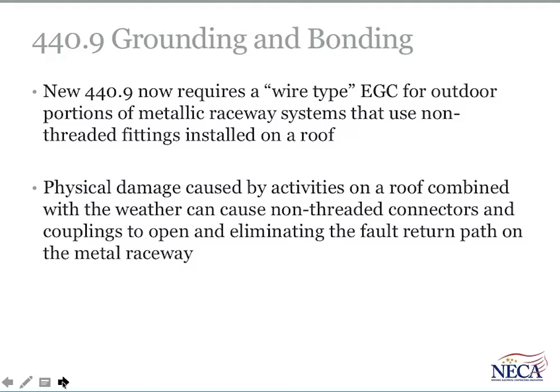So what that means is if it's intermediate metal conduit, rigid metal conduit, or EMT, and we're using compression-style slip fittings, the wire-type equipment grounding conductor is now required. The substantiation to drive the change was related to physical damage to a lot of those raceways being subjected to maintenance operations and so forth, where the equipment grounding conductor continuity through a metallic raceway could be impaired and loosened, as those conduits would tend to get damaged or be subject to those physical abuses. So by having the equipment grounding conductor contained, there's an increased amount of assurance that we will have an effective ground fault current path that is maintained, even if the fittings should loosen up under those types of conditions.